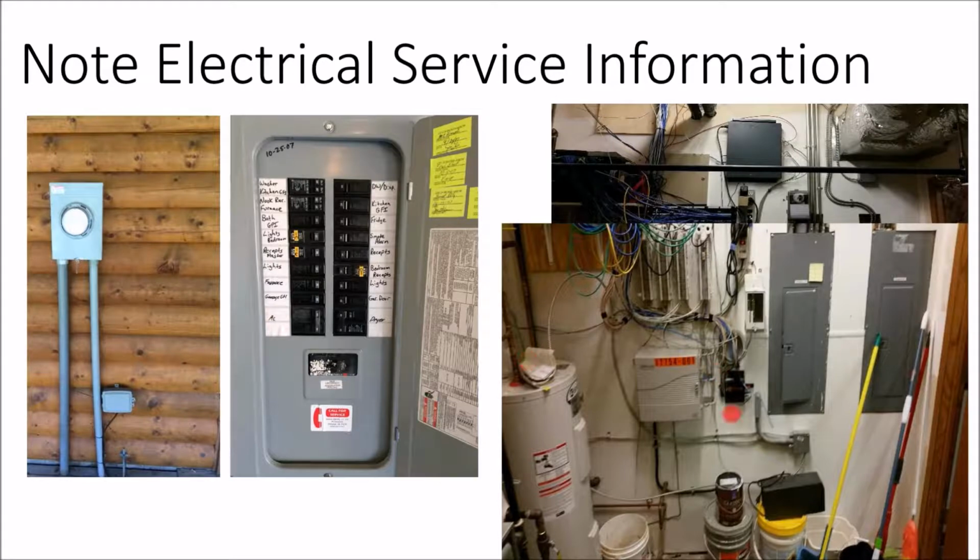And then here we have a commercial control room, and there's a number of code violations in this picture. So what that tells me is even if we have space inside the panel, we still want to consider a line side or supply side connection. So there's a lot of, this is what we have. We have where the power is entering the building.